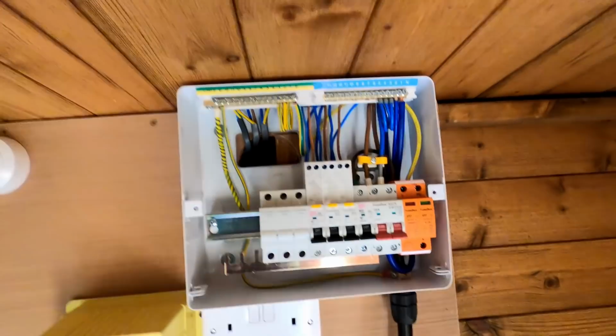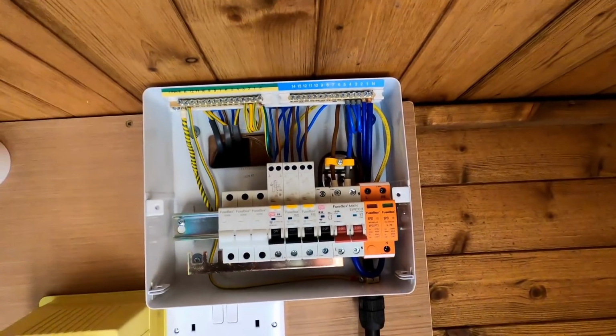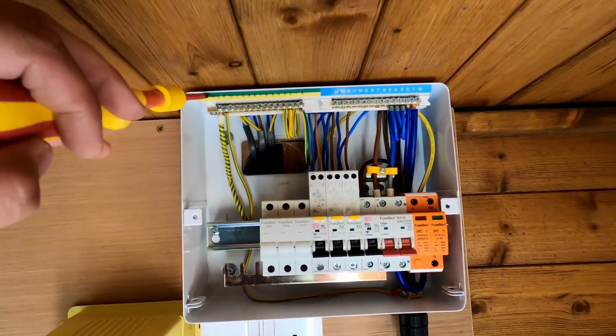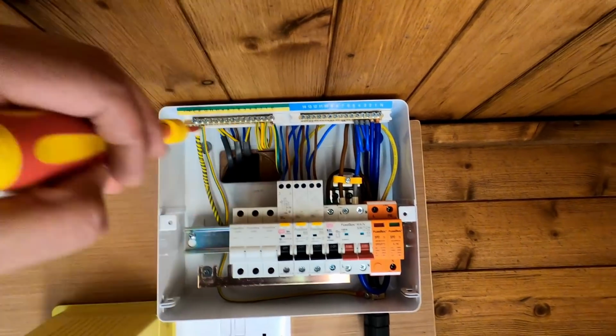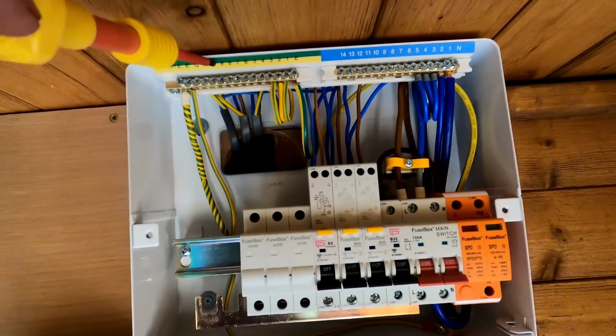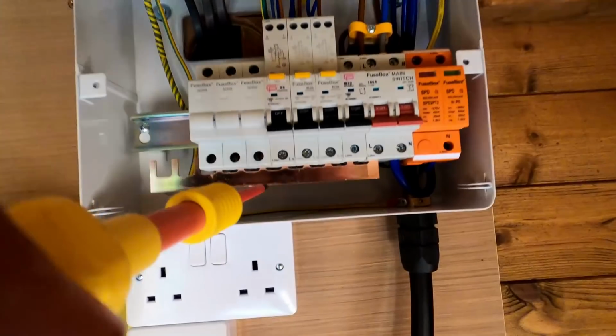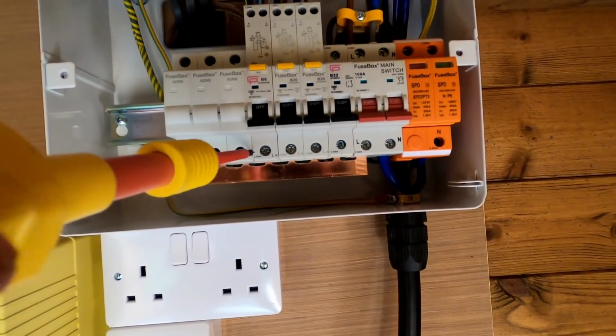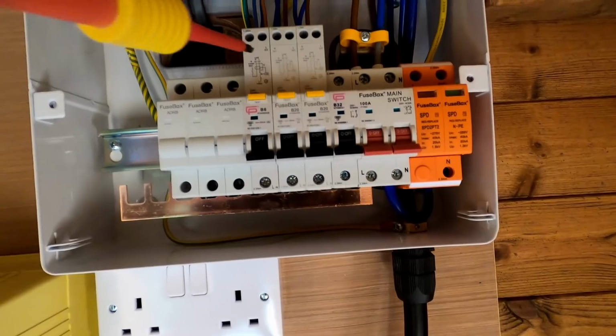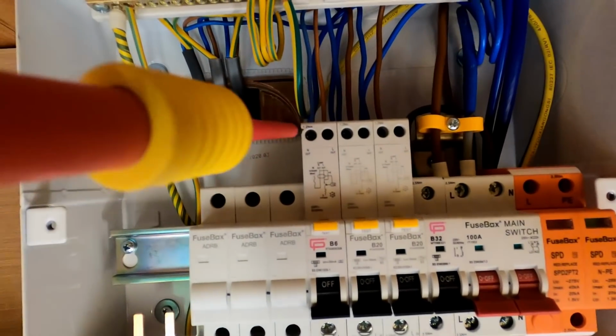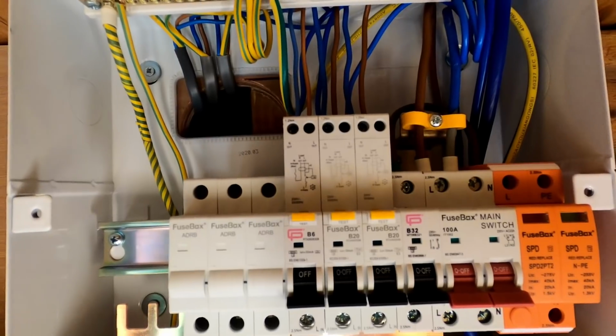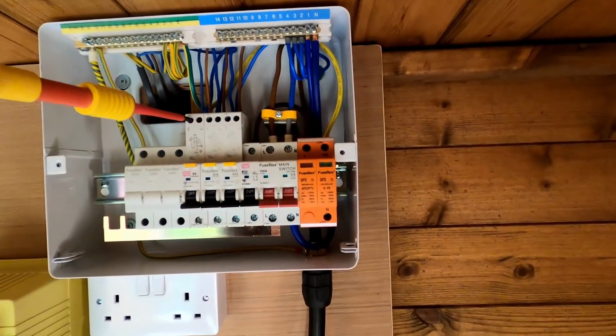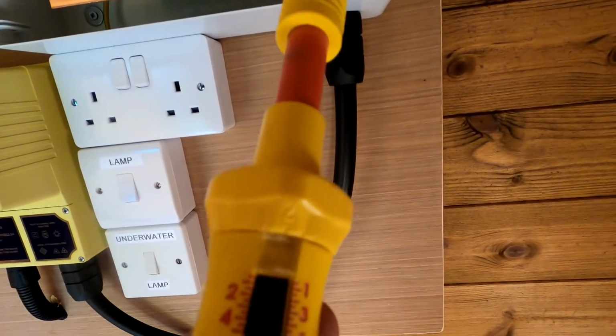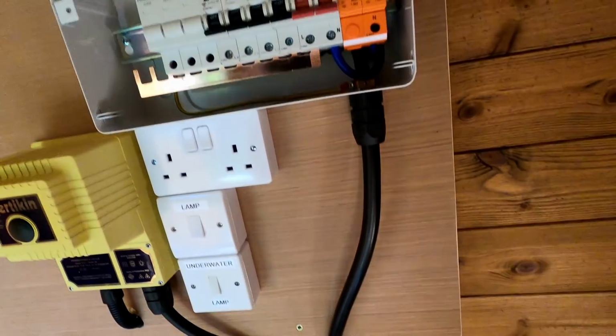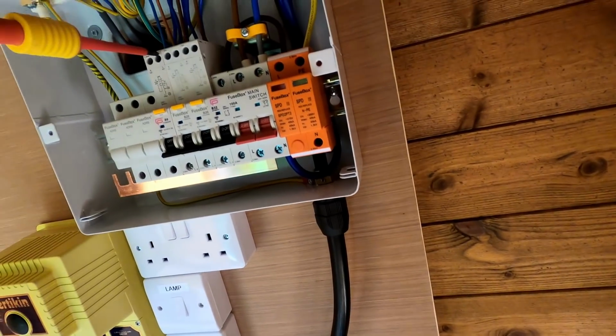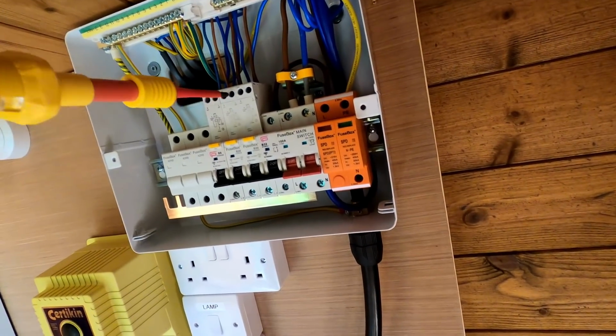One of the things I do like about these CP fuse box units is it actually gives you the correct torque rating on the labels. So for the CPC in the neutral bar it's 2 Newton meters. For the bus bar connections it's 2.5. And surprisingly on the RCBOs, the input connections 1.2. So I've set my torque screwdriver, I don't know if you can see that on there, but it's set to 1.2. Oh, clicky, excellent.